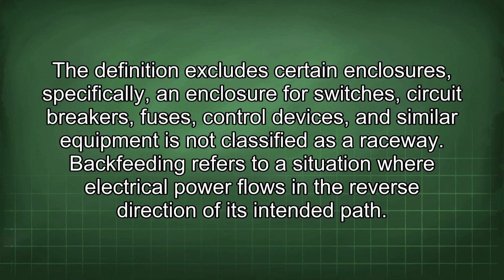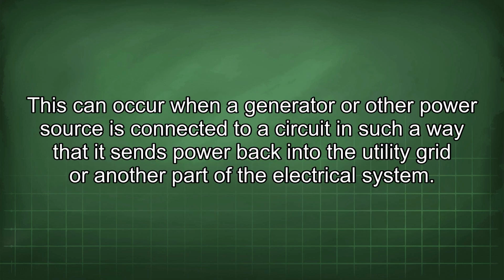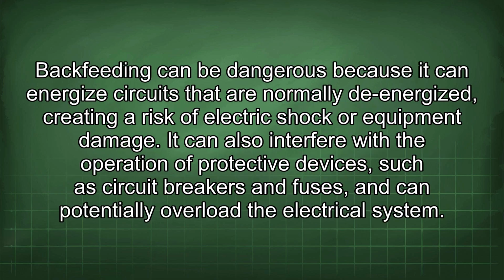classified as a raceway. Backfeeding refers to a situation where electrical power flows in the reverse direction of its intended path. This can occur when a generator or other power source is connected to a circuit in such a way that it sends power back into the utility grid or another part of the electrical system. Backfeeding can be dangerous because it can energize circuits that are normally de-energized, creating a risk of electric shock or equipment damage. It can also interfere with the operation of protective devices such as circuit breakers and fuses, and can potentially overload the electrical system.